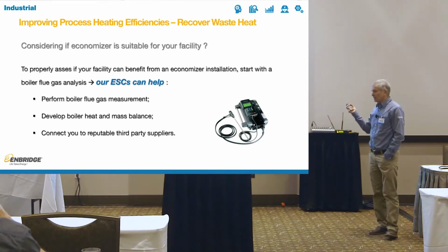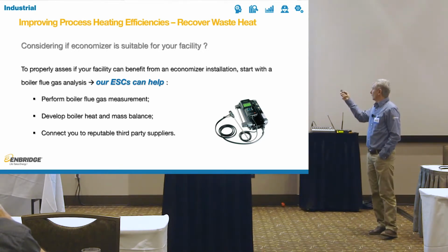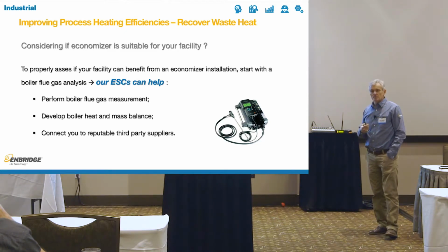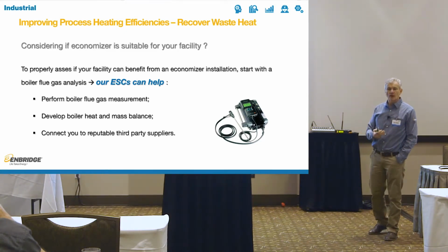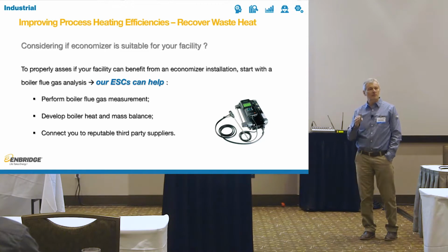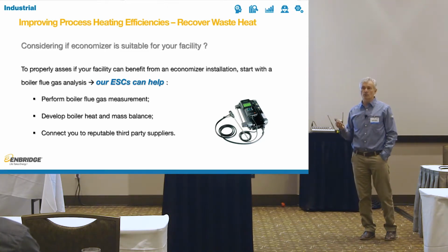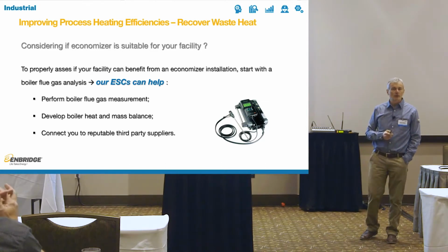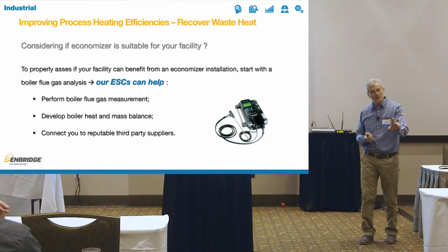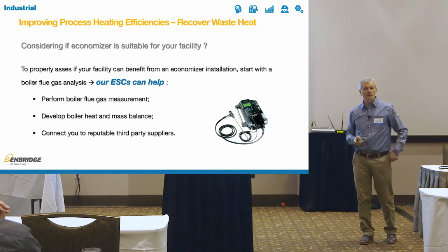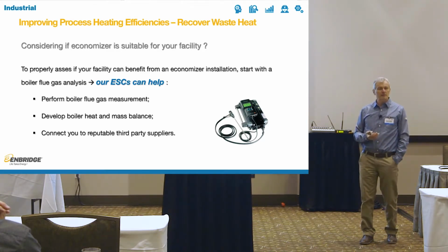So we often have questions about what the flue gas measurement looks like. We often have people calling us and saying, hey, can you come and help us install the economizer? We ask, well, what's your boiler flue gas look like? They're like, oh, it's good. It's like 80% efficient. But when we ask, can you show us a strip of the tester? Most people don't know that strip even exists.